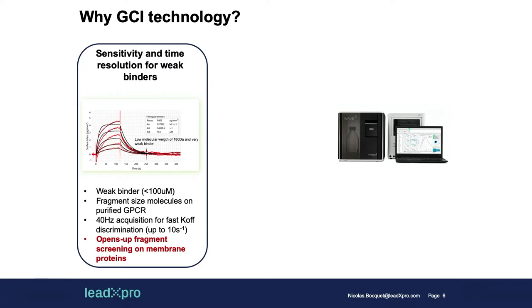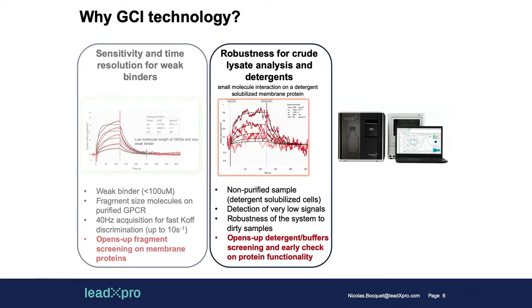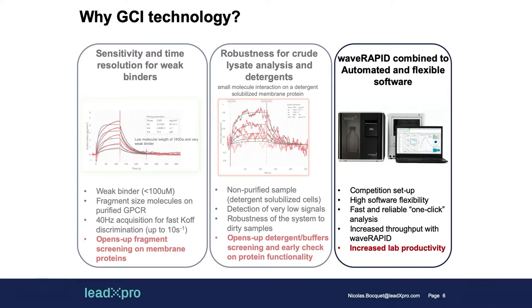First, we evaluated the sensitivity of the instrument, and the sensitivity turns out to be extremely high. We were able to record weak binders of very small size. For example, in the graph on the left, you can see a binder which is double-digit micromolar on the GPCR, and we were still able to record the kinetic data of this compound. In addition, we can acquire data at 40 Hz, which is very useful for weak binders with very fast kinetics, and it opens up fragment screening on membrane proteins. Sensitivity is really a crucial point for us, because when we purify a membrane protein, the percentage of active protein is never very high.